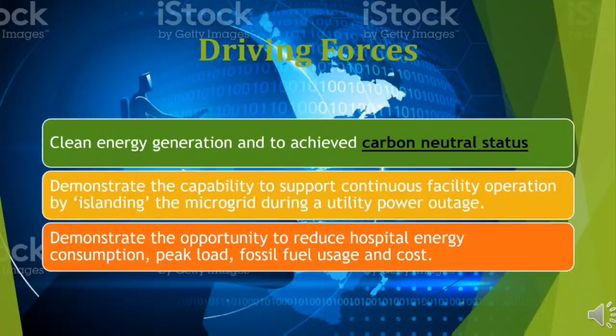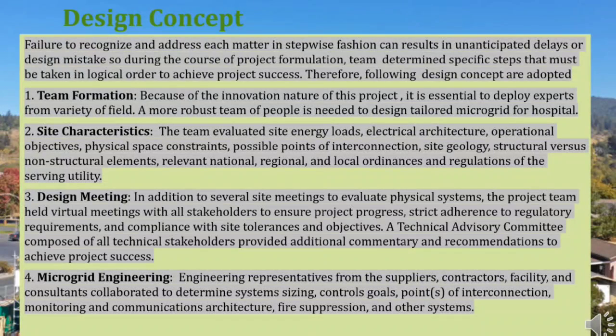One of the driving forces is to generate clean energy and to achieve carbon neutral status. Further, it is to demonstrate the capability to support continuous facility operation by islanding the microgrid during a utility power outage, and also to demonstrate the opportunity to reduce the hospital's energy consumption, peak load, fossil fuel usage, and cost. Design concept is important for construction of any project.